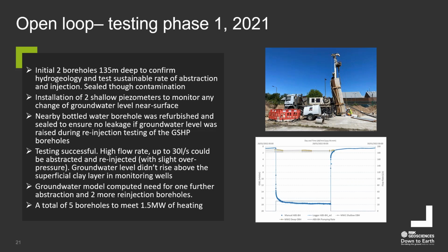So we drilled one borehole to the south of the site, one to the north. The local groundwater gradient was moving to the north towards the River Thames, which was about half a kilometre north of the site. As I say, we've drilled two shallow piezometers to monitor groundwater movement. We refurbished the local bottled water borehole plant to make sure that they weren't impacted by abstraction or re-injection from the ground source scheme. The two boreholes were drilled to 135 metres. The final diameter down at 135 metres was 300 mil.